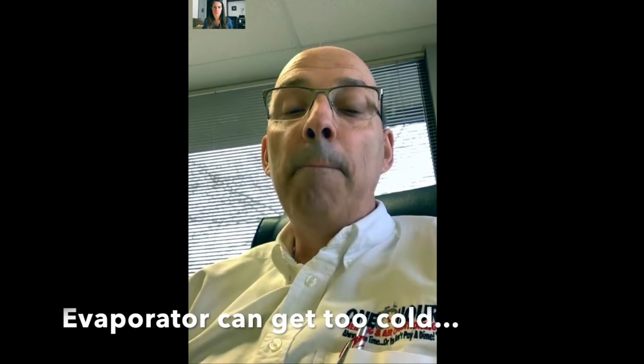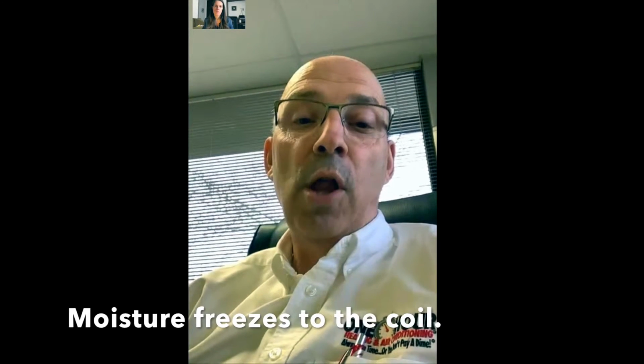So about the icing up—there's a strange phenomenon where an air conditioner can malfunction in different ways. It could be improper refrigerant charge, or a problem with airflow. But sometimes that evaporator coil operates too cold, actually below freezing, below 30 degrees. When that happens, the moisture we're pulling out of the air freezes onto the coil and literally turns into a block of ice.